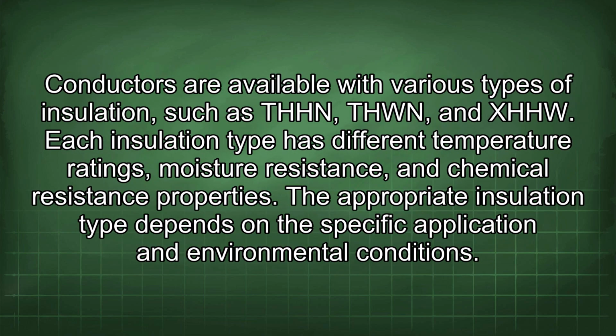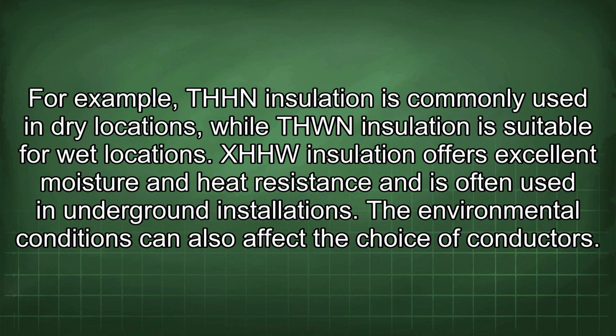Conductors are available with various types of insulation such as THHN, THWN, and XHHW. Each insulation type has different temperature ratings, moisture resistance, and chemical resistance properties. The appropriate insulation type depends on the specific application and environmental conditions. For example, THHN insulation is commonly used in dry locations, while THWN insulation is suitable for wet locations. XHHW insulation offers excellent moisture and heat resistance and is often used in underground installations.